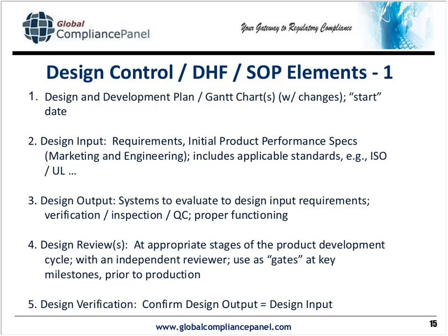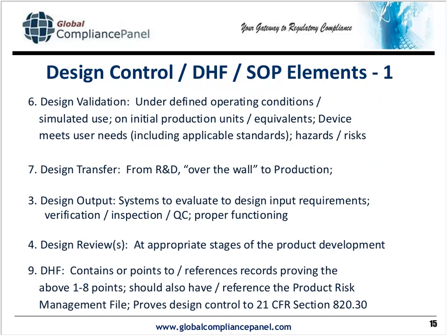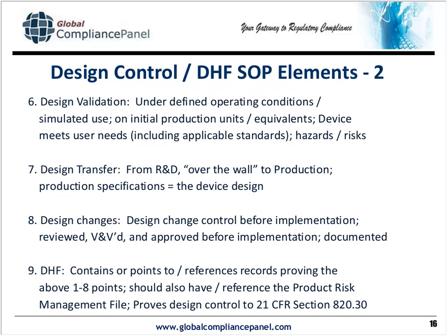Again, that's a series of inspections, tests, checklists, etc. Matrix, if you will. Design validation, we talked about that earlier with that slide from the FDA. But again, that's a series of verification steps showing that you've proven that your design input or your product as originally anticipated has been resulting in a production prototype that meets that intended design or requirement.